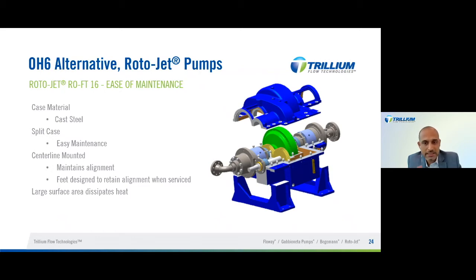And with one size, we can change the gear ratios as well as the pitot tube. You can also accommodate the same pump for future conditions, which means in 2 or 3 years time, if you have to upgrade the flow or the head, it's very likely you can use the same pump. All you have to look for is that the motor is accommodating the future condition.